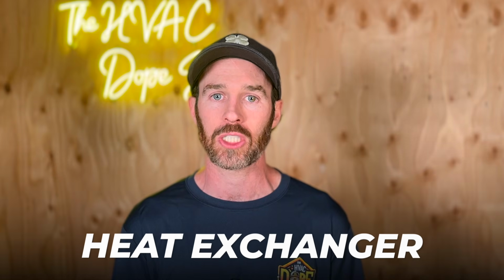And if we find it, it's much better than if the utility company finds it, because at least in Denver, Colorado, and I know it's like this in most metropolitan areas, if you have Xcel Energy come out and they find a crack in the heat exchanger, they will shut off your gas, and sometimes they will red tag the furnace, meaning they're shutting off the gas at the meter until you turn that back on. So you won't have hot water or gas for your furnace until that gets corrected, because it is dangerous. People do die from carbon monoxide poisoning every single year. It's very rare, but it is a very serious condition.